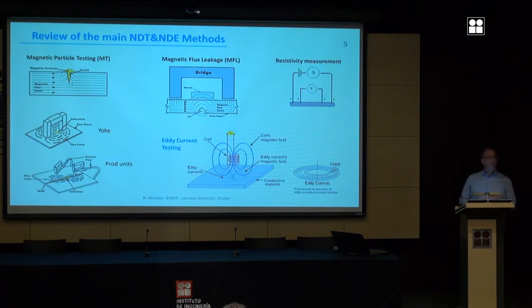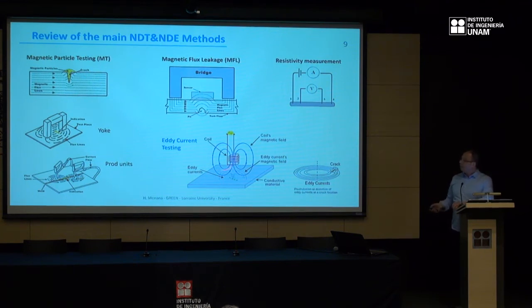And the most common one is eddy current testing. In eddy current testing, we have a sensor which is generally a coil fed by an alternating current. This coil will create an alternating field. If you put this coil above or near a conductive plate, the alternating field created by the coil will create eddy currents in the tested piece or tested sample. These eddy currents will create their own field that will oppose the primary field, the source field created by the coil. That will result in a change of the impedance of the coil.